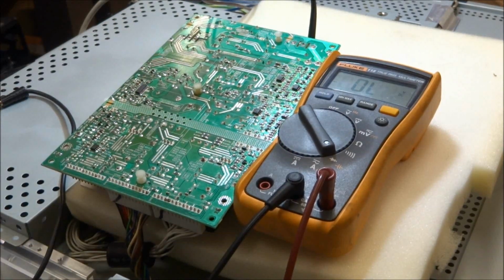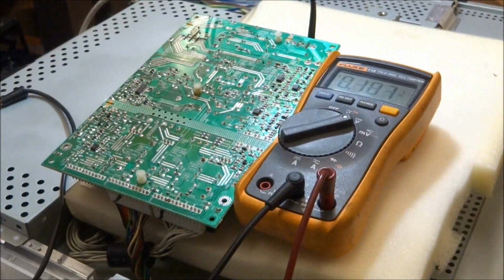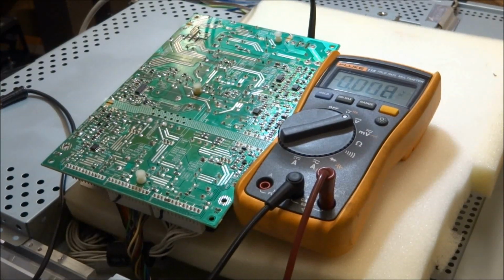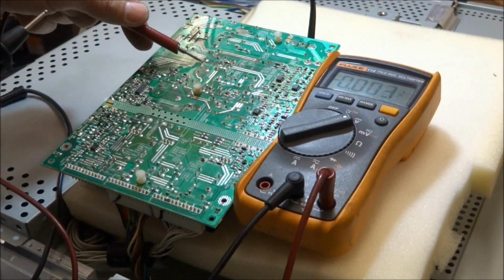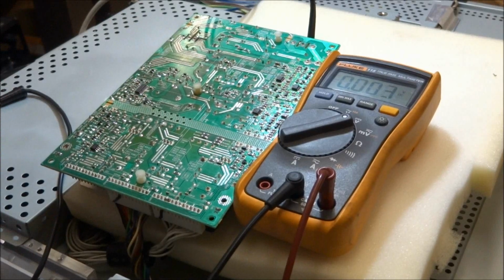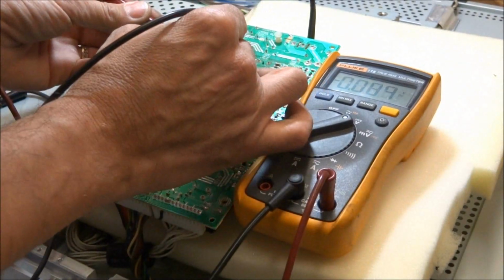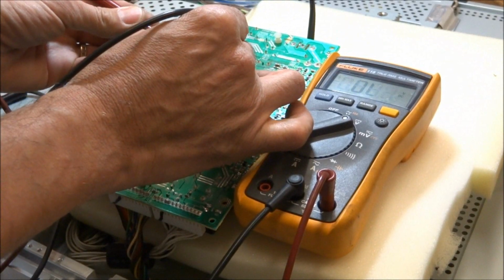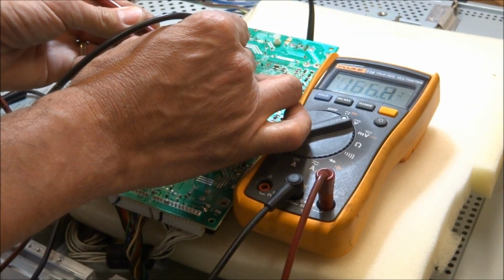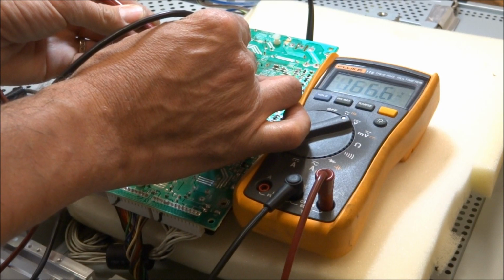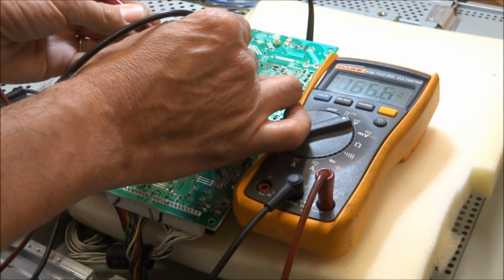So the next thing I'm going to do is put my voltmeter back in volts, and I'm actually going to measure the voltage on the main filter capacitor here. That's the big storage capacitor, and that's part of the power factor correction circuit. What I want to see on this one is about 350 to 420 volts when the set's run normally.